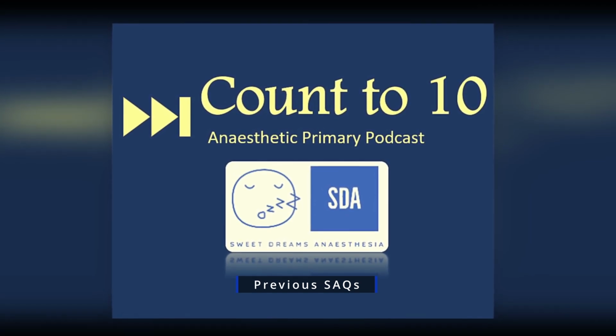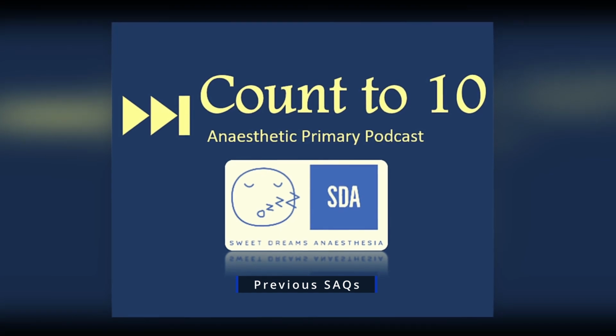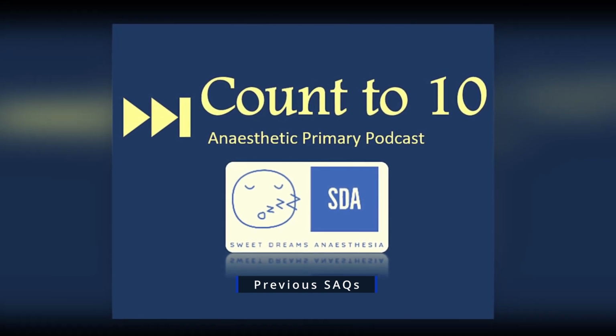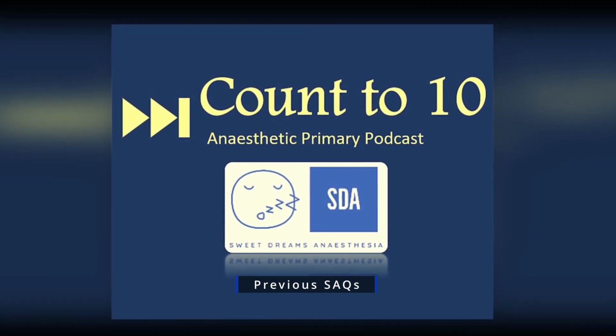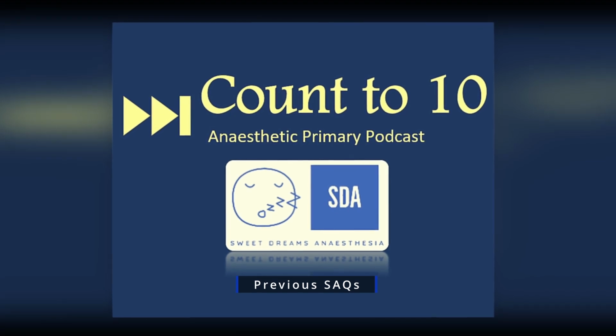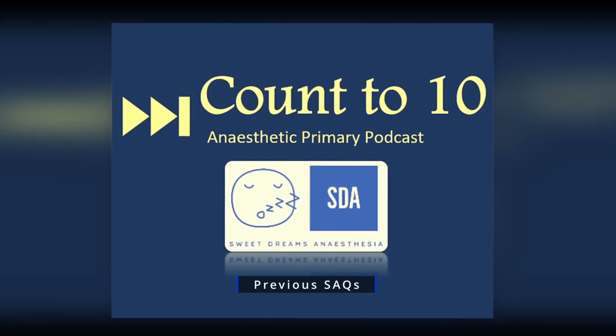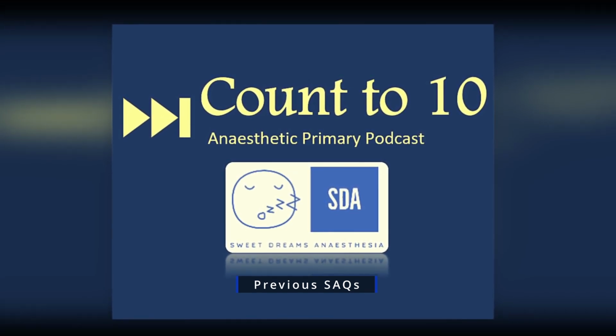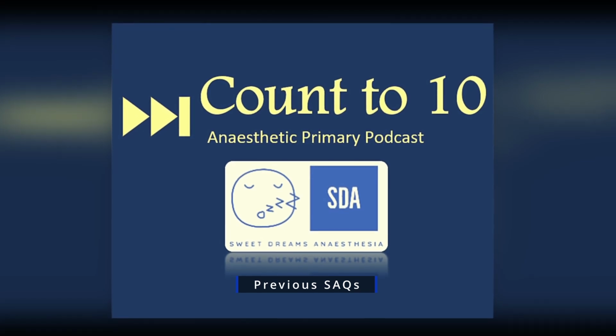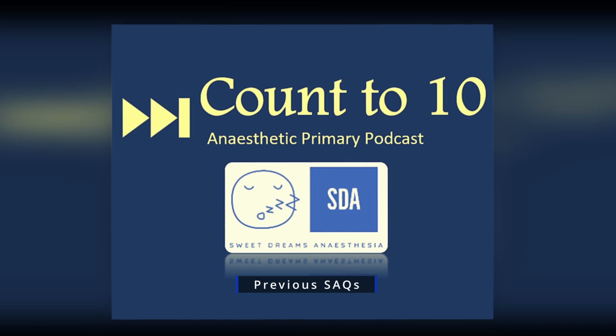The second type of analysis is the frequency domain analysis. So here you're looking at those epochs, those time interval packets. If you're getting an increase in frequency and a decrease in amplitude, you're going into a higher BIS reading. If you're getting a decrease in frequency and a higher amplitude, you're going into a lower BIS reading. Therefore, your depth of anesthesia is getting higher and higher.